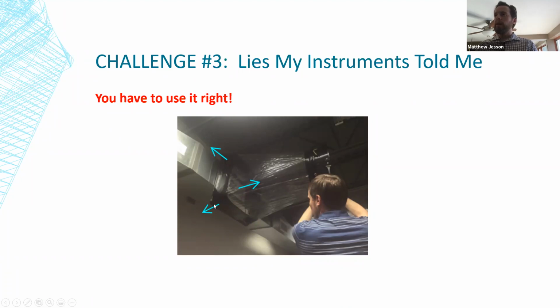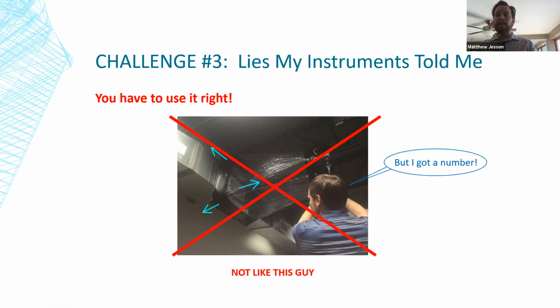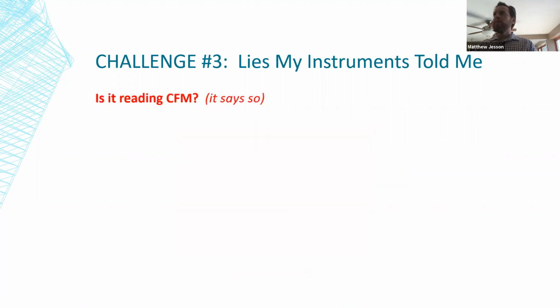So don't be like this guy, which if you don't know, that's me demonstrating how not to use a hood. My defense is I got a number. Yeah, you can certainly get a number, that's for sure. But is it reading CFM? It says so. Like I said before, the hood has a meter that's usually mounted to the base of it, and you hold it up to a diffuser, you hit the button, it clicks a few times usually, and then it'll tell you 153 CFM. So it's important to understand how it's getting there.